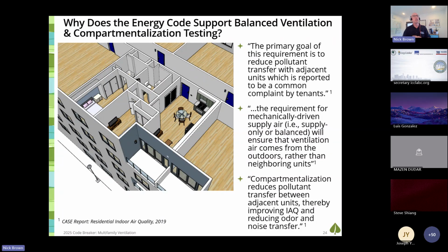So here are some quotes from the case report when these proposals were being evaluated. The primary goal of this requirement is to reduce pollutant transfer with adjacent units, which is reported to be a common complaint by tenants. So when you explain this to your applicants, when you've got a multifamily situation with shared walls and roofs and floors, an exhaust ventilation system may not be bringing in fresh air, it may be bringing in neighbors' stale air. Hence the need for compartmentalization testing to make sure these units can operate semi-independently.